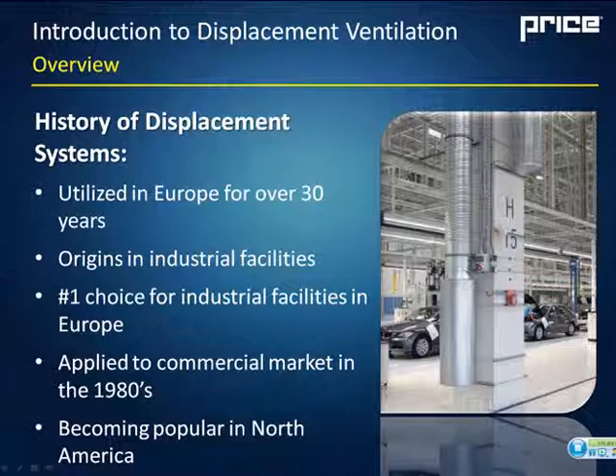So starting off with the history of displacement systems, displacement is not really a new technology. It's been utilized in Europe for 30 to 40 years at least. It had its origins in industrial facilities simply because it was a more effective way of removing contaminants as opposed to a mixed system. And it actually still remains the number one choice for industrial facilities in the European market. In the 80s, they started to apply it to the commercial market, and now we're seeing it become popular in North America as well.